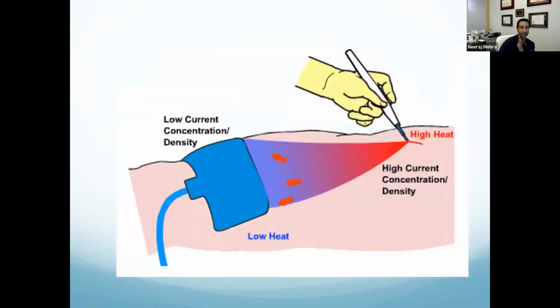So this is what's happening in our circuit. Those electrons are still flowing through the patient, but the energy flowing out of your electrode is at high current density. So you have high current density here, which is creating a high amount of electrons flowing, and that's creating high heat. But those same electrons are passing through the patient. If you were to measure the temperature here, you probably would get a subtle change in temperature. You just wouldn't notice it because it's not enough to cause tissue damage.